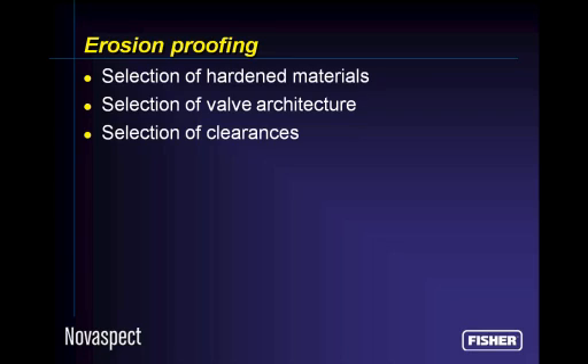We might use a straight-through valve like a butterfly valve or a segmented ball valve, because it's a line-of-sight valve. If I picked it up and looked through it, I could see right through it, compared to a globe valve, which has a lot of twists and turns. And we control the clearances of valves that are going to be used in erosive services. Gritty substances will have a tendency to collect in places that have close tolerances, thus restricting the motion of the moving parts, and that will make a bad control valve. So these are some of the ways that we erosion-proof one of your control valves in that kind of service.